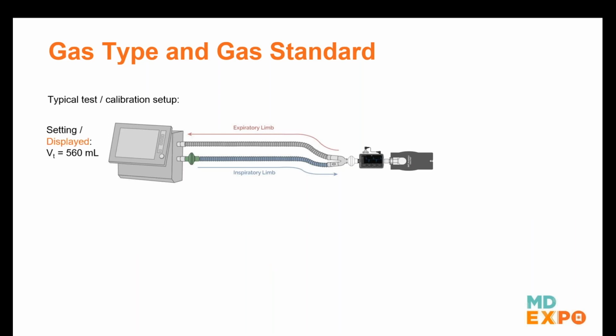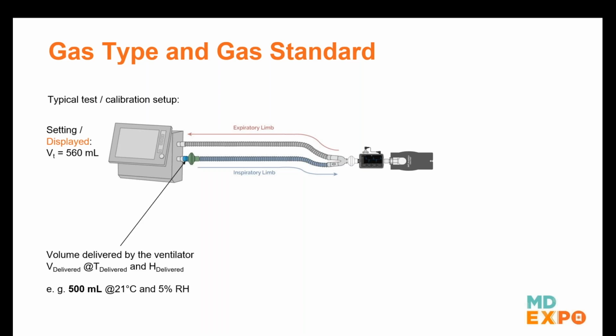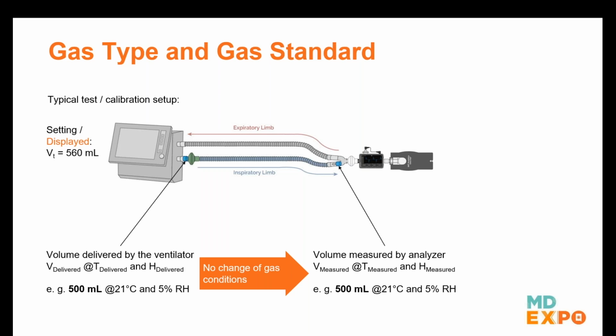So if we look at this and we say, all right, the ventilator's saying that it's delivering 560, we know that its output is really 500 because we converted ATP to BTPS on the ventilator display, right? There's no change in the gas as it goes down the patient circuit. It doesn't get warmer, it doesn't get more humid, so its tidal volume doesn't increase. So when it gets to our analyzer, we're measuring 500. We're actually measuring what the ventilator is putting out, even though the ventilator is saying it's more than that. Again, that's that convenience conversion for the operator. So what can we do?